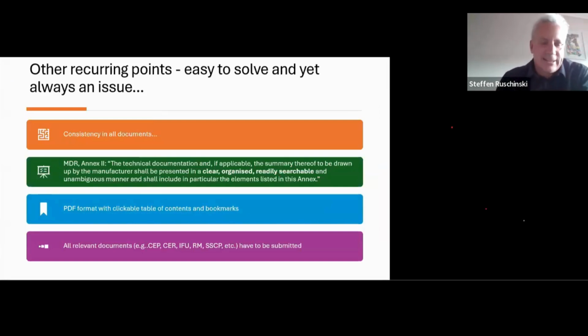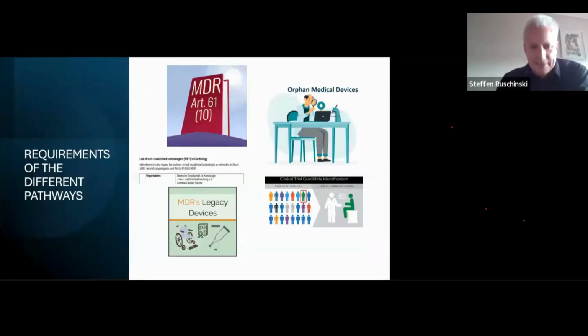Please look that we have consistency in all documents. Technical documentation according to the Annex 2 of the MDR, and if applicable, the summary thereof to be drawn up by the manufacturer shall be presented in a clear, organized, readily searchable, and unambiguous manner, and shall include in particular the elements listed in these annex. It should be submitted in a PDF format, and we need a clickable table of contents and bookmarks. And of course, all relevant documents, the CEP, CER, IFU, risk management, SSCP, or whatever, have to be submitted so that nothing is missing. So these have been the biggest pitfalls and the parts of the notified body there.